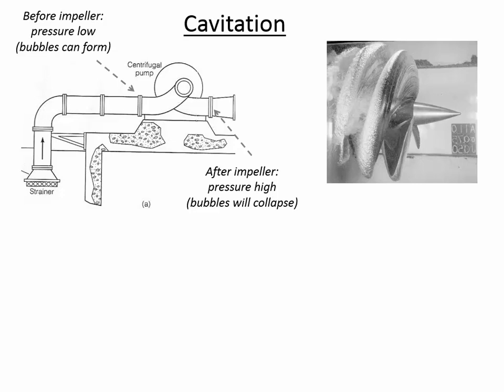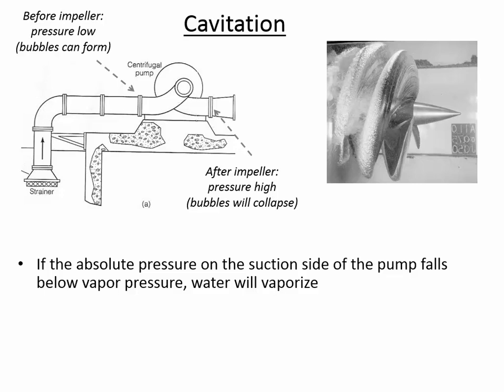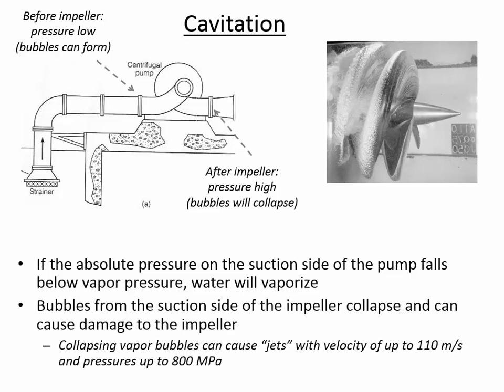And that one little bubble, the individual force of its shock wave may not be too damaging, but over the long term, millions and billions of these little bubbles collapsing and sending a shock wave towards the material that the pipe and the impeller are made of can cause a lot of damage to the impeller. The pump actually gets pitted and the material will start to erode. In lab measurements, they've actually measured jet velocities when the bubble collapses and the water shoots inward towards the center of the bubble. The velocities can reach 110 meters per second and pressures of up to 800 megapascals. And so those are pressures about 100 times greater than anything we'd expect to see inside a pipe network.